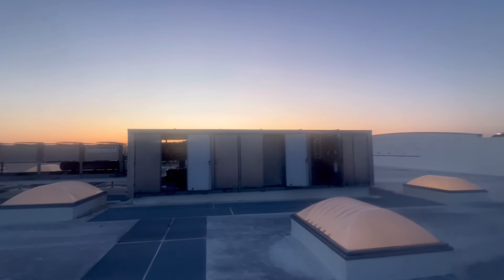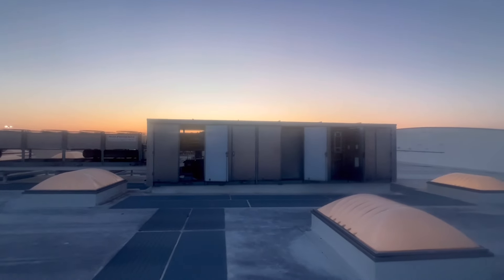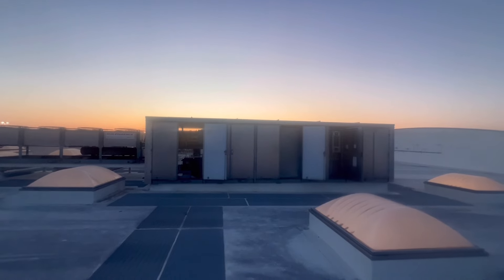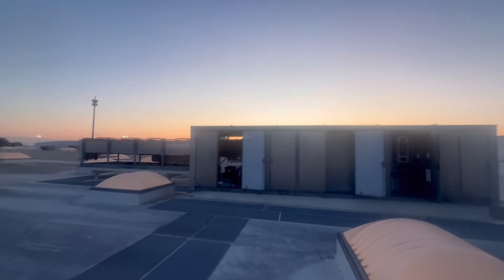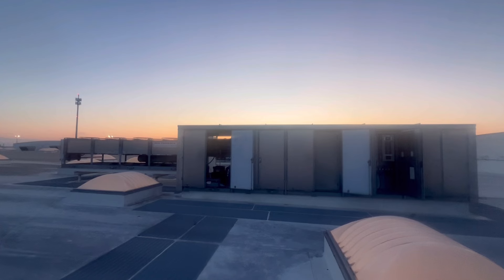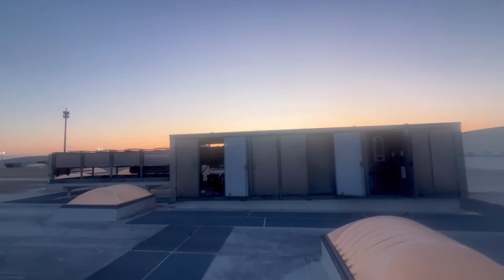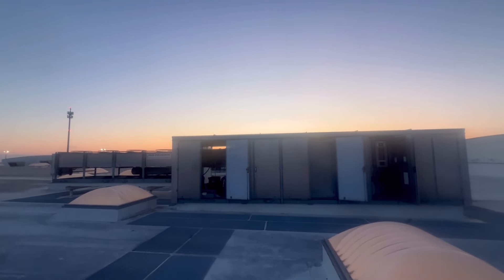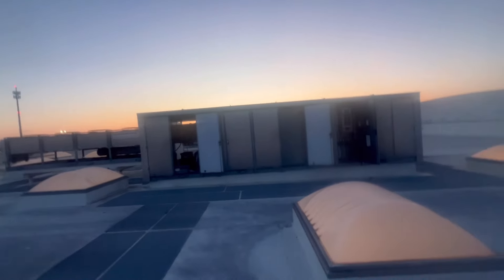But I'm gonna leave it at that — they got frozen up. Let me know your thoughts down below. It was funny because somebody said Novar sucks, but Novar is not bad at all — it's a pretty good system. But it sucks that something unplugged can cause a domino effect like that. To me, they lost all those cases due to a 24-volt plug not being connected right — all that product.